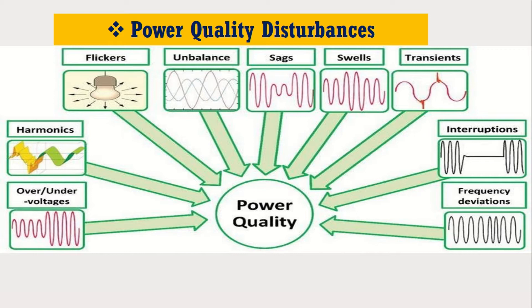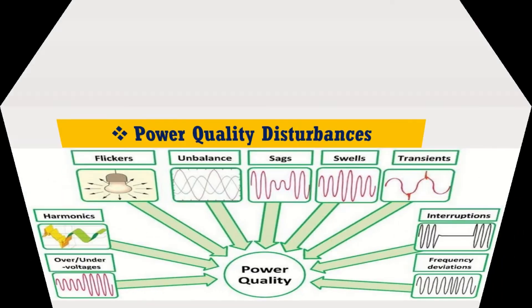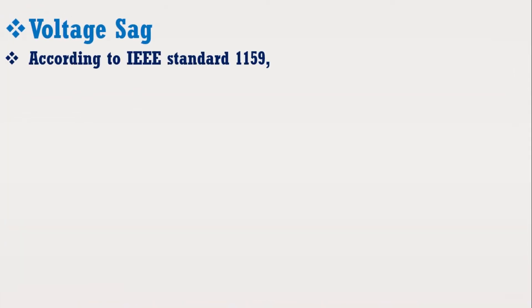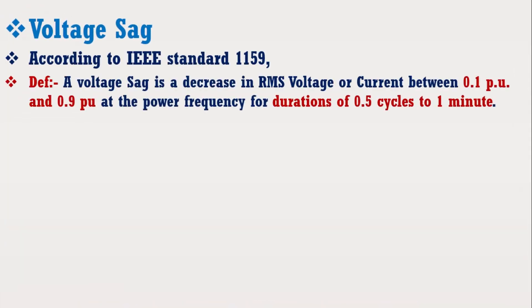Power quality research is the study of various phenomena that cause power quality disturbances to occur and the development of mitigation strategy. According to IEEE standard 1159, a voltage sag is a decrease in RMS voltage or current between 0.1 and 0.9 per unit at the power frequency for durations of 0.5 cycle to 1 minute.